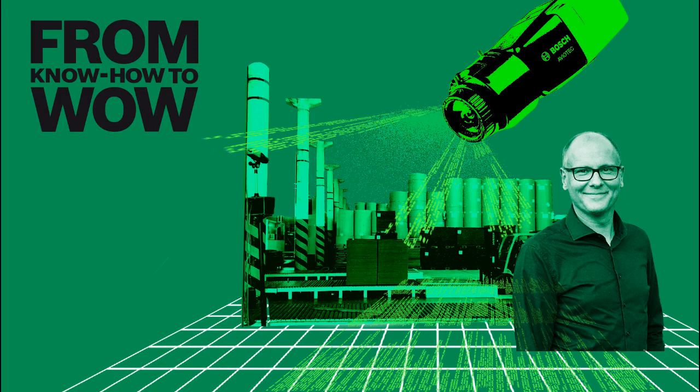Our Australian friend Shane Raffel looks at fires with expert eyes. In a lab at Bosch, engineers develop another expert eye for reading the language of fires — a smart camera that works as a smoke and fire detector. Søren Wittmann is the project manager, and the product is called Aviotec. Aviotec is developed for areas or applications where normal, classic fire detectors have problems to detect flames or smoke. A smoke detector is mounted at the ceiling — the smoke has to travel from the fire source to the detector, and this might take minutes. In industrial applications with ceiling heights of sometimes 20 meters, if you can detect within seconds, the fire is caught very early when it's very small. The damage is lower, and it's easier to extinguish.